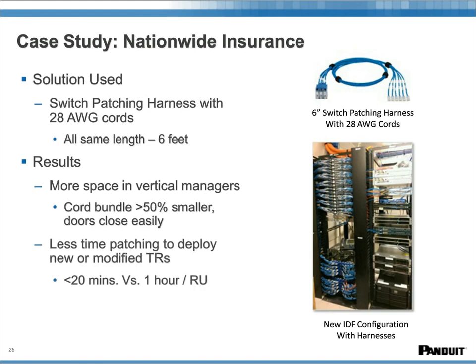Well, that gave me more space in my vertical managers. I was able to close the door. It was a lot nicer, clean looking. Time for patching a switch, like you said earlier, cut it from one hour down to about 20 minutes. My low voltage installers, they really like the 6-packs and the ease of use with cabling up a switch, which really saves me money too. Before I always had 2 guys at 4 hours, so that was double the labor. And it's becoming a constant configuration across all of my locations.